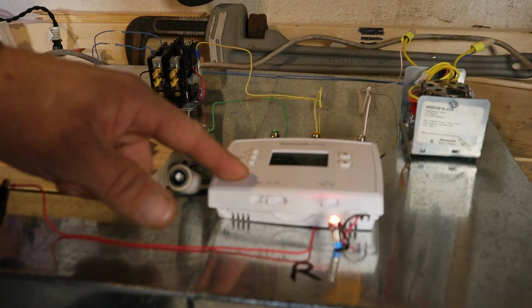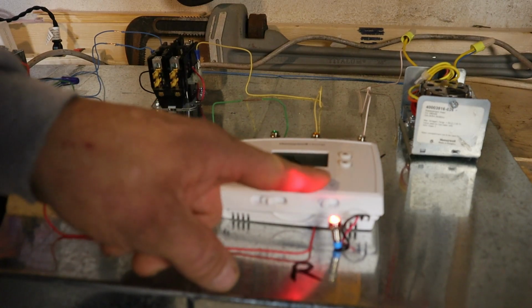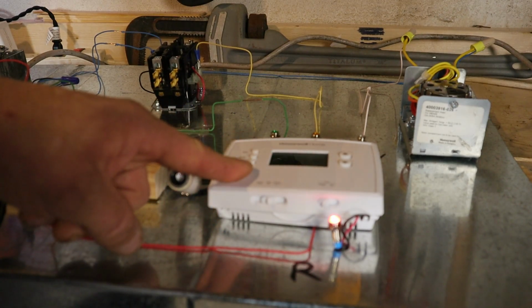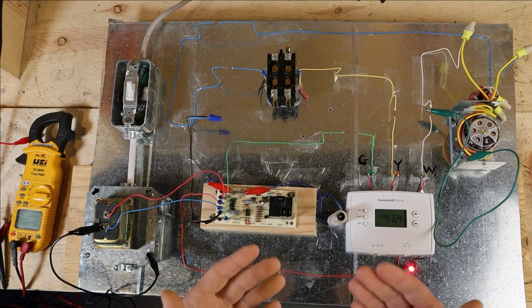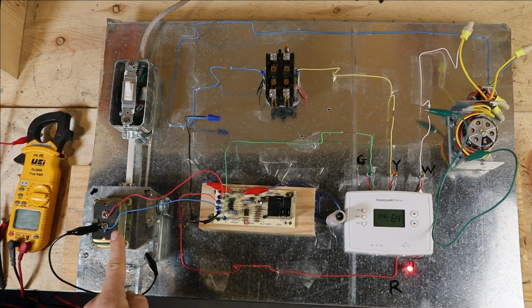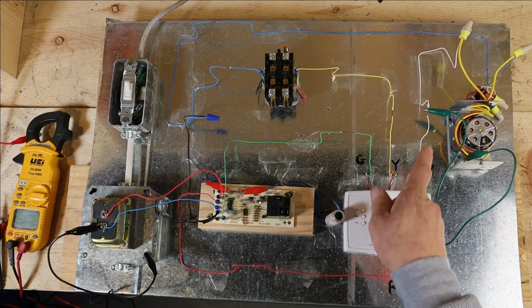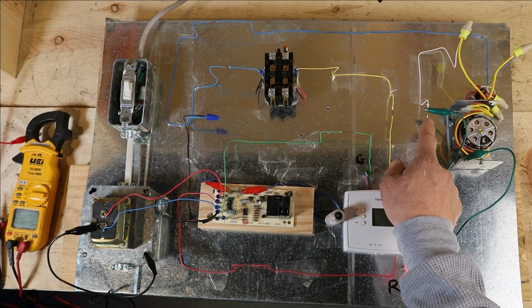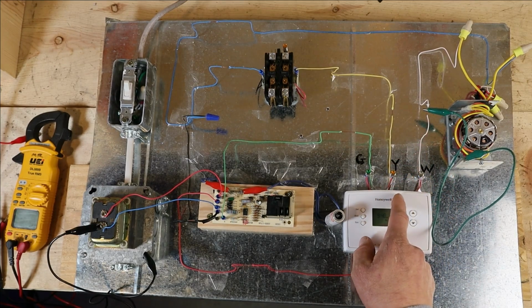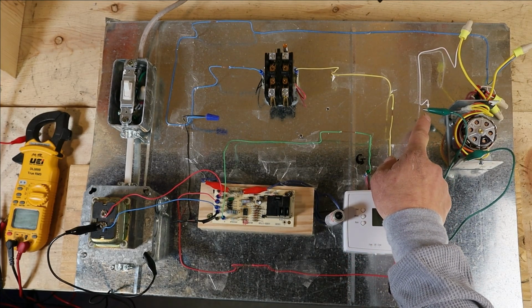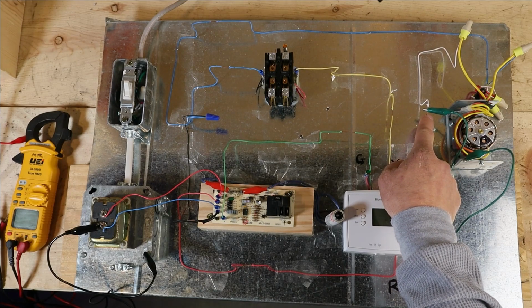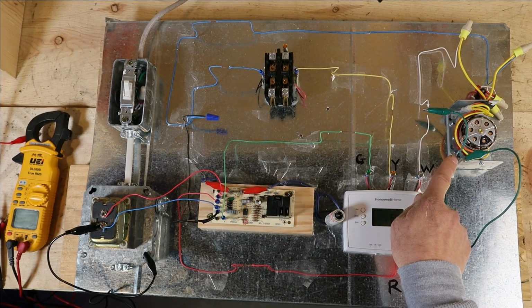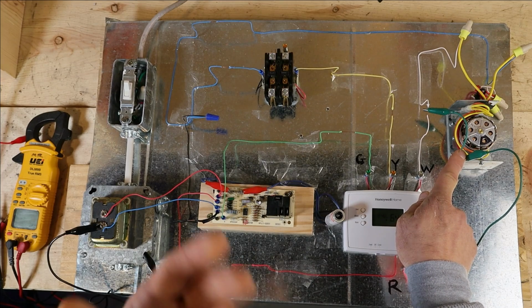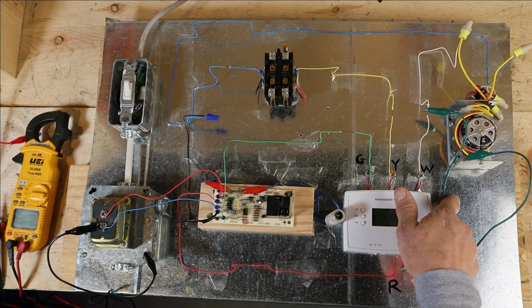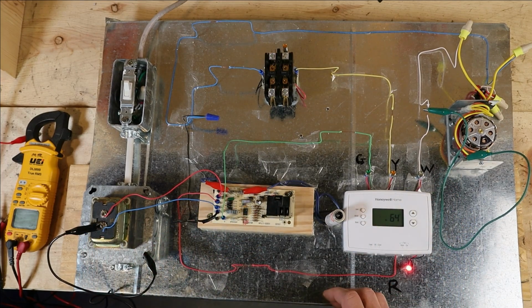Armed with the knowledge of whether you're dealing with a floated or a grounded secondary allows us to take a second step, which is usually the first step in a lot of these videos: go to the thermostat and try changing to different modes to see if our fuse is popping in a particular mode. So to demonstrate this, we're going to start off with a grounded secondary, and I created a short on our heating wire. That's the white wire coming off the W terminal on our thermostat, and you can see I have a green alligator clip going directly from the bare wire to the metal of our zone valve box here.